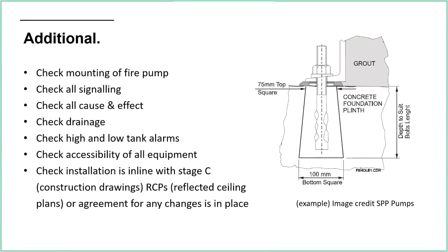It's not the sprinkler contractor's responsibility to do the drainage, generally speaking, but you just need to make sure that is in place. High and low tank alarms, check accessibility of all equipment. So again, that should have been planned out well in advance, but can you actually get to everything for service and maintenance? And if you can get to everything, is it safe to get to everything? If you've got to duck under a load of pipes, if you've got to crawl under something, is that safe to do so? Now is your final chance to bring that up and get some changes made if necessary.